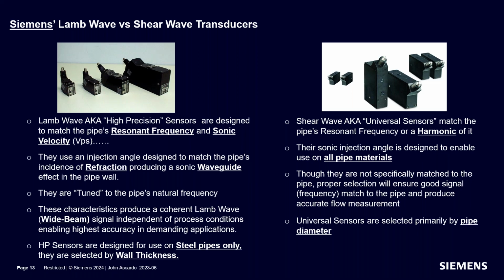So these characteristics produce the coherent Lamb wave signal, which remains independent of the process conditions. And so even though application conditions are changing, the meter is able to maintain its accuracy. One of the conscious decisions we made back in the day when we introduced them for the 990 was that they're for steel pipe only.